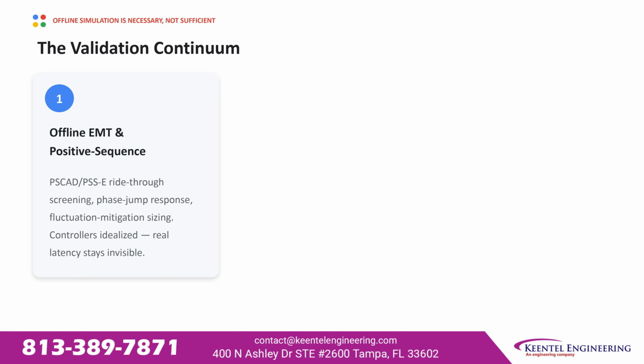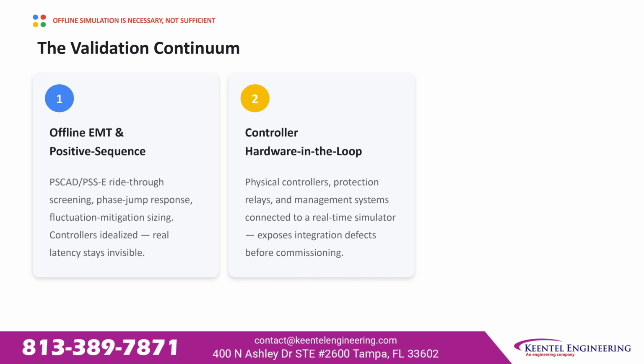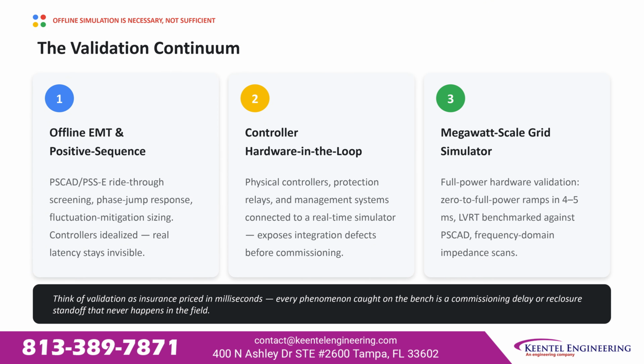Validation runs across 3 stages. Stage 1 is offline EMT and positive sequence modeling, PSCAD and PSS/E, ride-through screening, phase jump response, and fluctuation mitigation sizing, but with controllers idealized so real latency stays invisible. Stage 2 is controller hardware in the loop, physical controllers, protection relays, and management systems connected to a real-time simulator, which exposes integration defects before commissioning ever happens. Stage 3 is the megawatt-scale grid simulator.